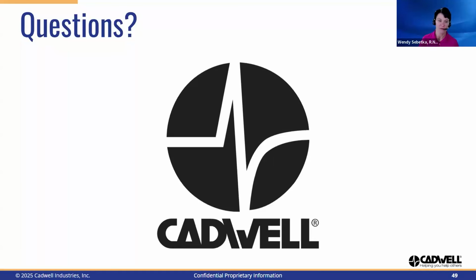Recommendations on managing electrical interference when performing nerve conductions and EMG in intensive care units with multiple electrical appliances going on. ORs and ICUs are very difficult environments. A lot of those other devices that are working can't be shut off. You just can't shut off a vent. That's counterproductive to why we're there. So generally what we would try to do is unplug all of the devices we can. A lot of times the bed can be unplugged, the bear huggers can be unplugged. If the bed is on a rotating cycle, then that can generally be stopped.